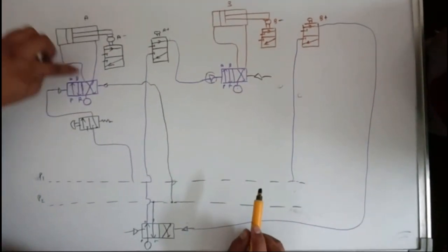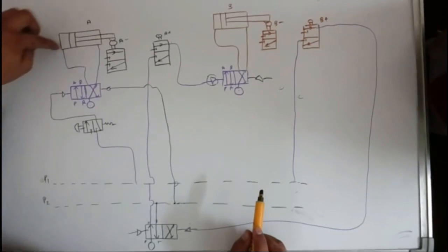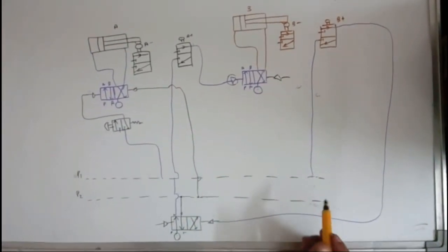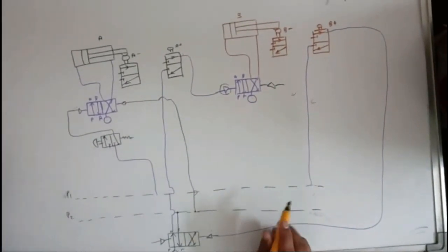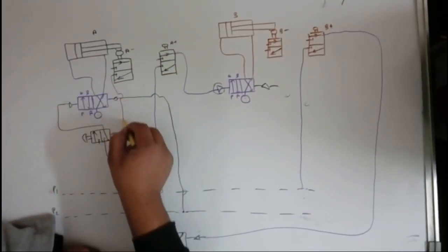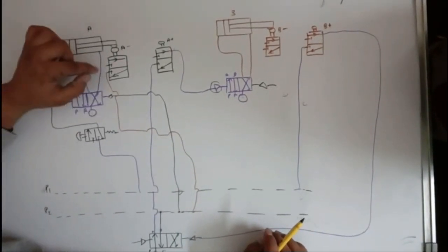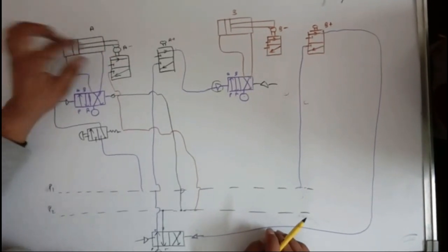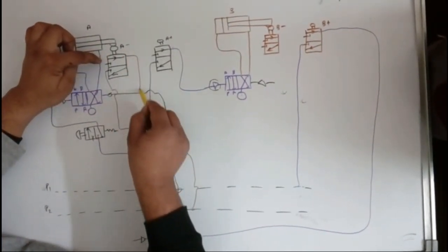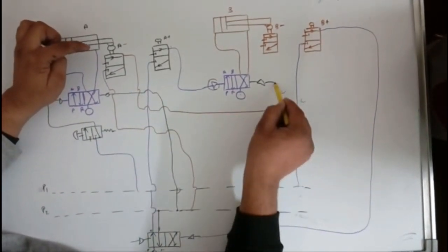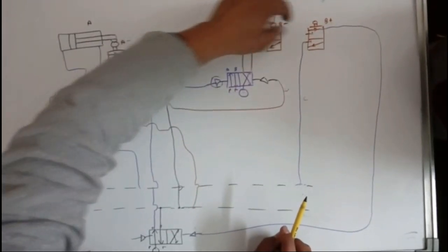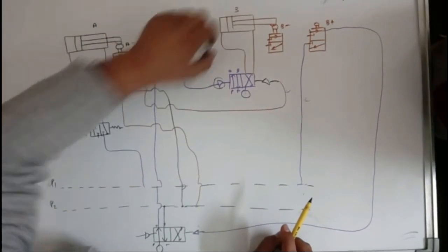Air starts entering from one side and leaving from the other, causing cylinder A to retract. When the piston reaches A−, the limit switch is pressed again. This changes the valve position and pressure from P2 flows through, operating the pilot for cylinder B's valve, changing it so B retracts — achieving B−.